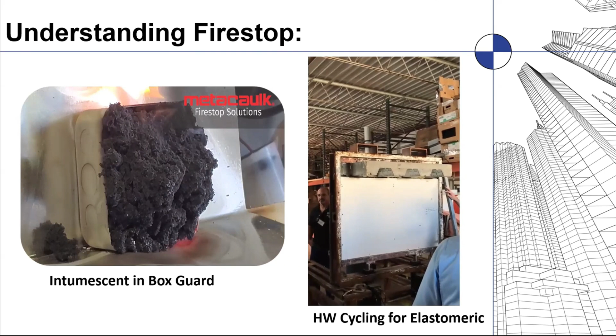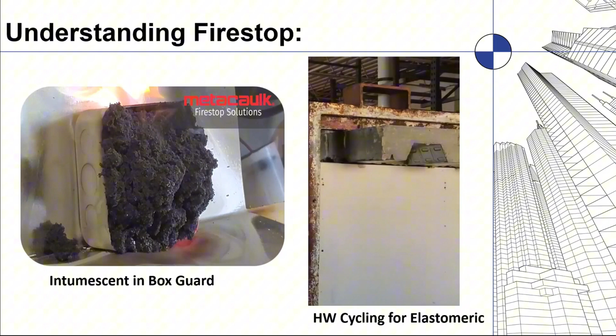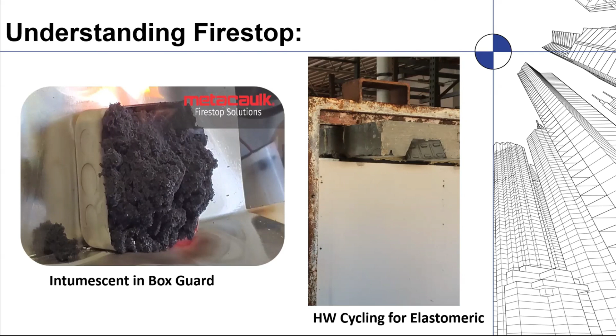On the right-hand side is an elastomeric action. This is a corrugated concrete deck in a cycling machine with a gypsum wall, simulating the deflection of a concrete deck bouncing up and down as people walk across it or cars drive over it, so there's relief to keep the gypsum from being crushed or cracking. The fire stopping materials are placed in between there.